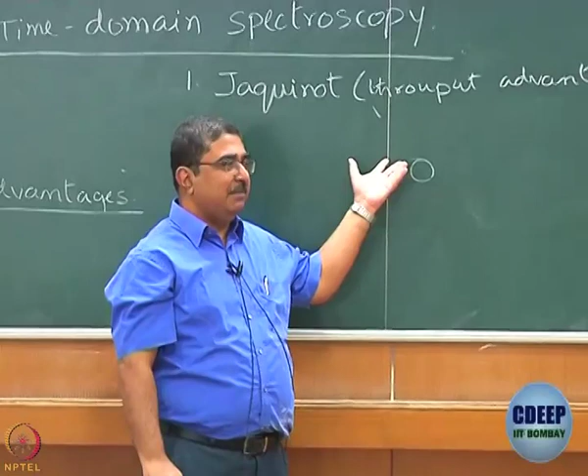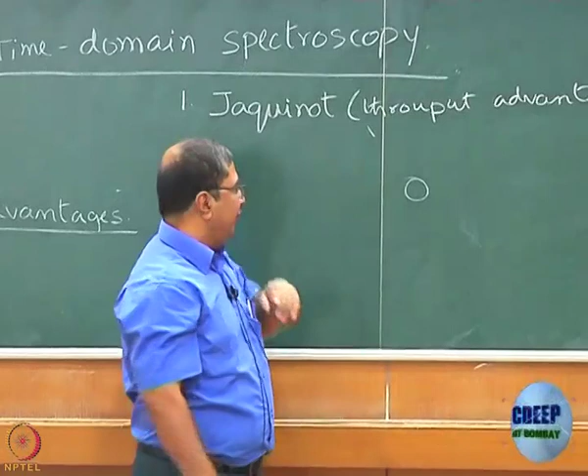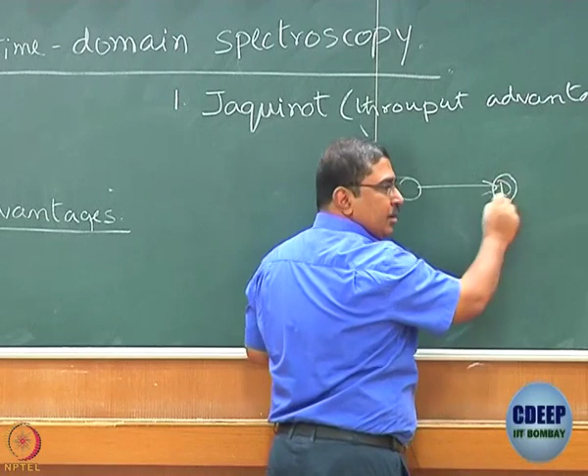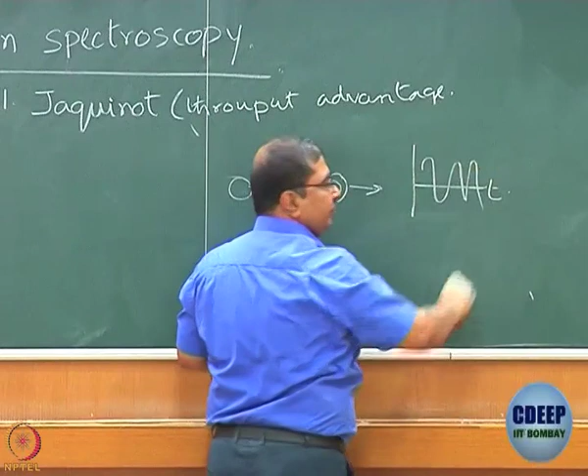Now, see, you measure say from 500 to 5000 centimeter inverse in steps of say 3 centimeter inverse. How many points would that be? 1500. So, you have to measure these 1500 points one by one. Now, all the intensity that you collect is going in at the same time when you do a time domain measurement, because you are not using a monochromator. We will see very soon how the time domain measurement is actually done, but schematically you can think like this. This is your source. When I say source, it can be the light source or an emissive sample, or it can be the light from the light source after passing through the sample in transmission. That just goes into your detector, which is capable of producing a time domain output.